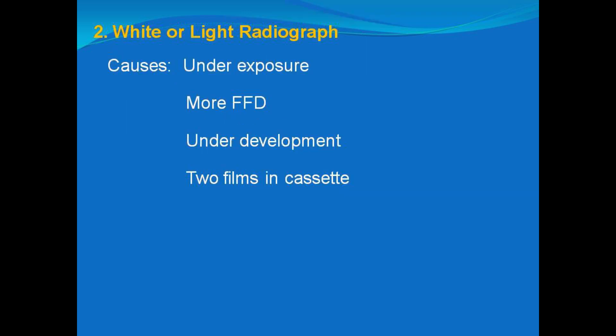The second radiographic fault we get is a white or light radiograph. This can be due to underexposure — using low kVp, low mA, or short exposure time — or we may be using more FFD than 90 centimeters, meaning our tube head and table distance will be more. Next is underdevelopment: the film is underdeveloped due to less concentration of solutions, particularly developer, or we may be using less time in the developer, resulting in a light or white radiograph.